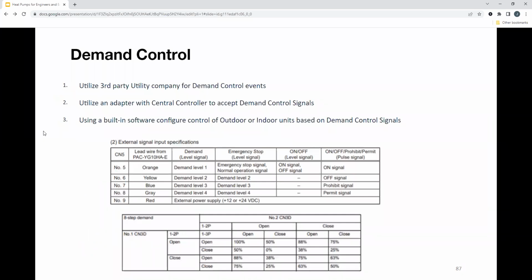That was peak cut. And then the other option is demand control, which is, again, using that third-party utility company for demand control events. What you're not doing is adding all that energy allocation and pulse metering on. You're actually just reducing the capacity of your compressors, right? And the utility company is controlling that. All you have to do is add an adapter at the outdoor unit itself, and then it'll give basically voltages based on what your capacity needs to be. So in a demand control event, you sign up for this, your utility company says, all right, you need to be at 50%. They're able to control that and set your compressor to 50%.